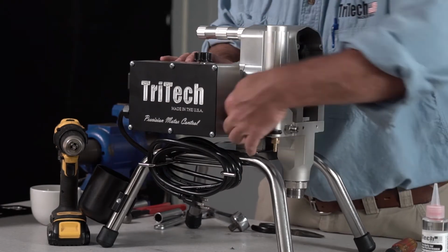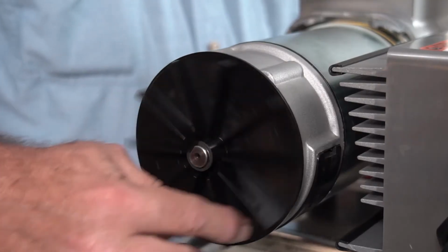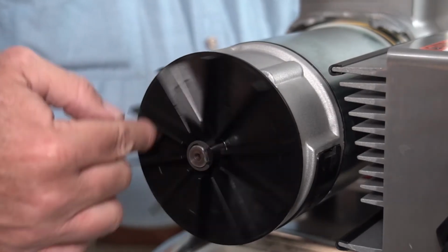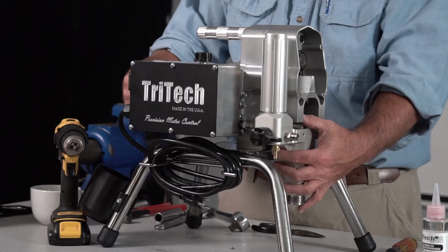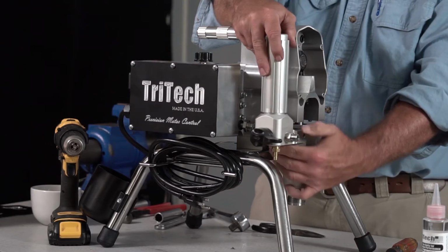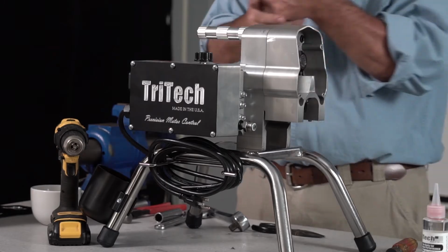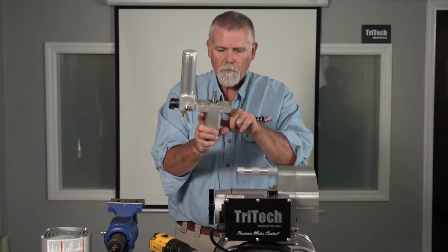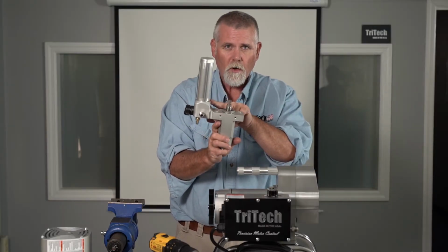So our bolts are removed, our transducer is removed, and we go ahead and we spin our fan, and that pushes the fluid manifold down. Then we can just slide it off of the pump. So this is your pump and your filter, all one part.